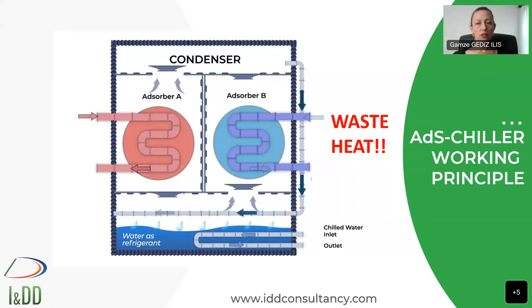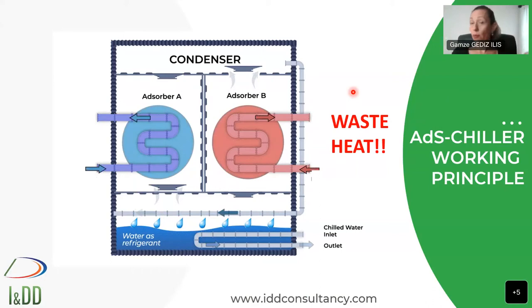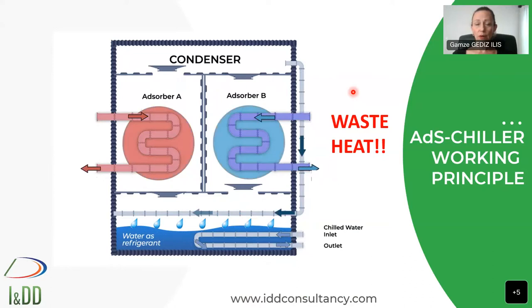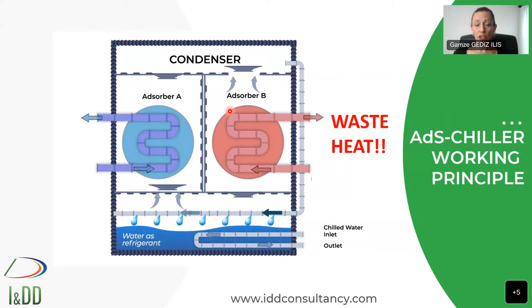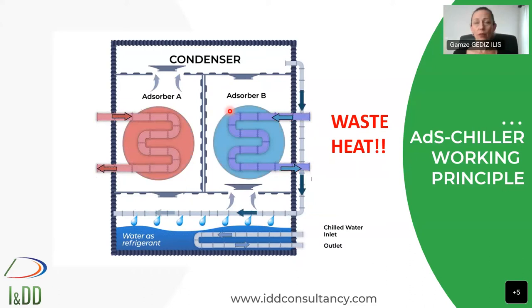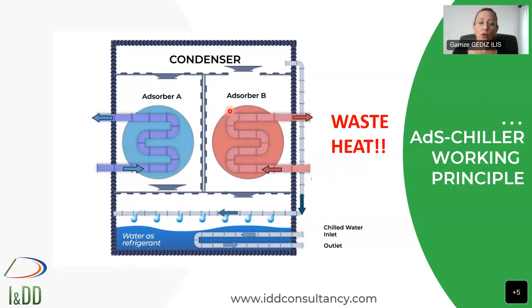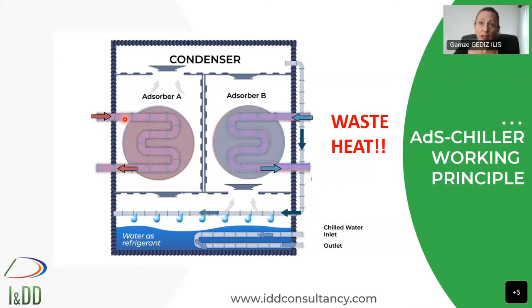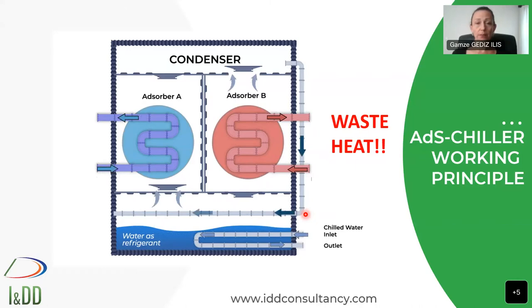Here is the working principle of the adsorption chiller. In general refrigeration systems, we have a condenser, evaporator, compressor, and expansion valve. But here, instead of the compressor, we have two adsorbers working simultaneously. The third input — to produce chilled water — is not electricity but waste heat: for example from a geothermal plant, a solar plant, or a chimney. Thanks to the physical phenomena between water and silica gel, we generate chilled water that you can use wherever you want.